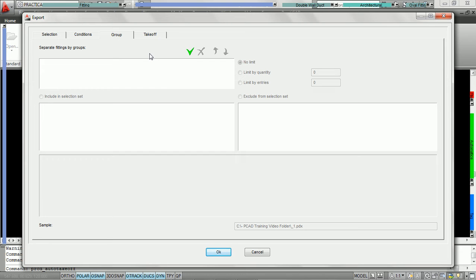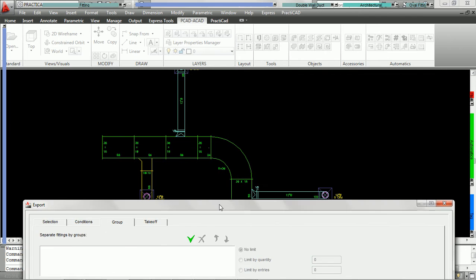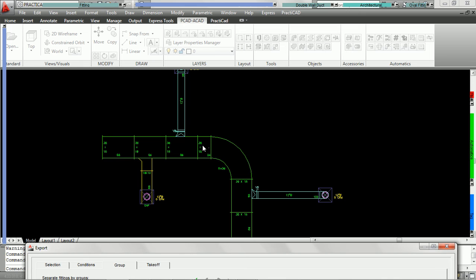In order to do that, we must first decide how many groups we'd like to use. Currently on our drawing, we have a duct system that consists of three different colors: green, blue, and yellow. The green duct happens to be drawn with a 6 inch water gauge specification, representing our high pressure group. The yellow duct was drawn with a 2 inch water gauge specification, representing our low pressure group. The blue duct is under the fabrication level order only, because this duct we're buying and we'd like to order it. So we'd like three groups: high pressure, low pressure, and order.